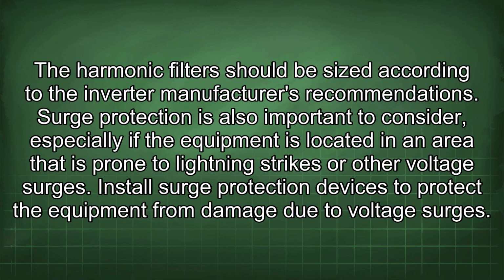The harmonic filters should be sized according to the inverter manufacturer's recommendations. Surge protection is also important to consider, especially if the equipment is located in an area that is prone to lightning strikes or other voltage surges. Install surge protection devices to protect the equipment from damage due to voltage surges.